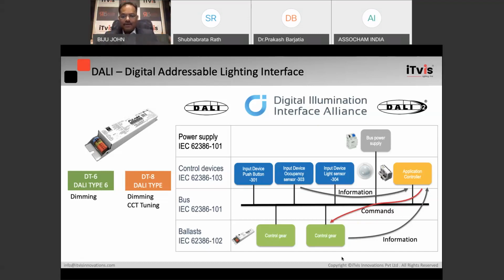Now, what is the whole architecture in a lighting management system? The control gear, which is the driver of a luminaire, can give messages to the application controller, and it can also receive commands from the application controller. What messages does this driver give? It gives the power consumption of that particular luminaire. It gives the dimming graph of that luminaire. It can even give alerts, like my temperature is exceeding the limit, or I am going to die in so many hours because my working condition is not good. So a lot of messages can go from this DALI driver to the controller.